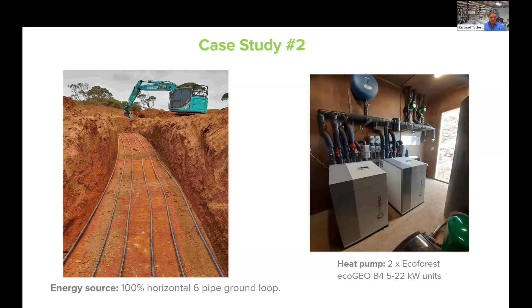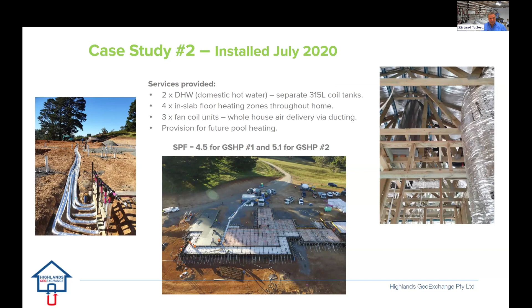A couple more slides of the installation. There are two separate hot water systems splitting the home, a large floor area for hydronic floor heating, and three large ducted fan coil units for heating and cooling, plus provision for pool heating. Each of the two heat pumps was connected to its own hot water system, which is why we've got a slight variable on the SPF, the seasonal performance factor. COP measures heating only, EER measures cooling, so these machines combine EER and COP to give you the seasonal performance factor — energy in versus applied energy out.